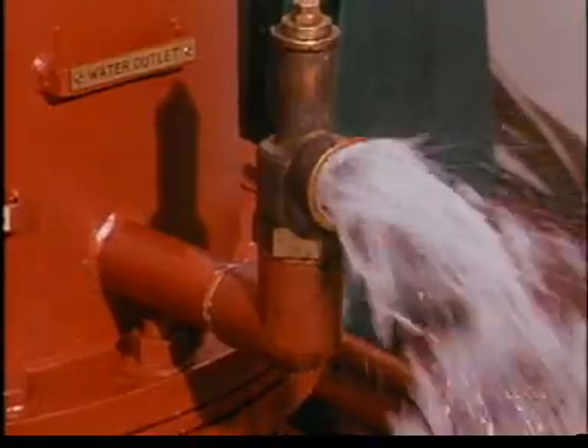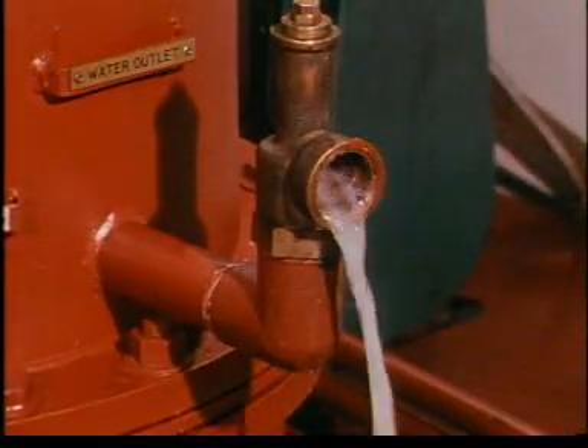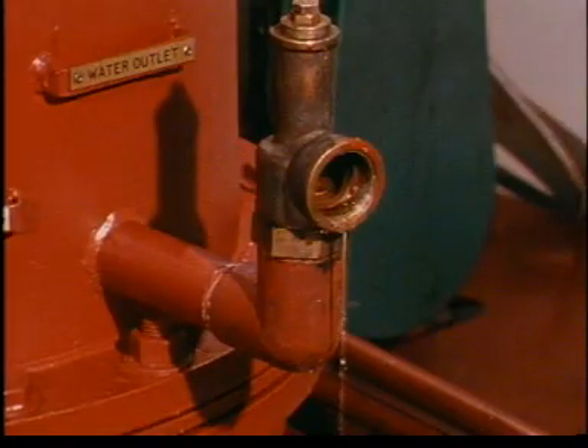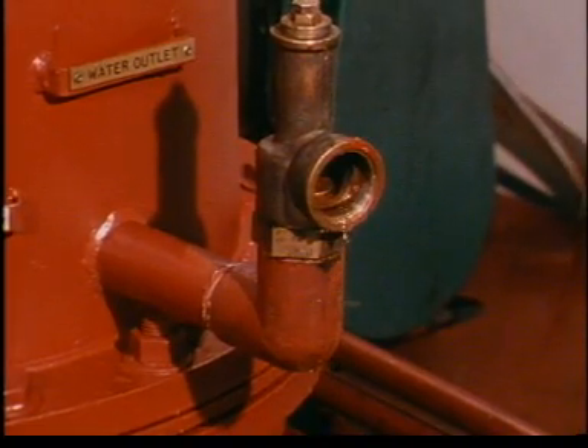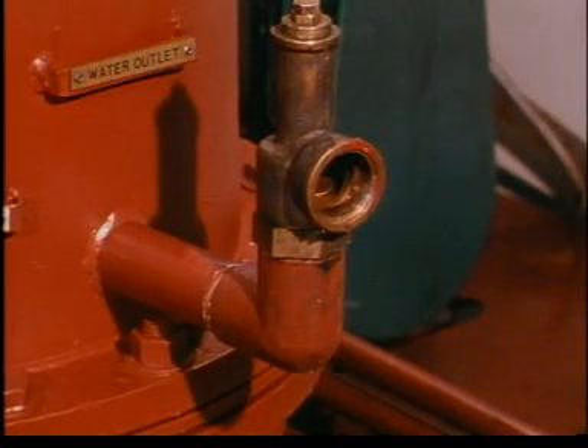There is a spring-loaded water discharge valve, which closes automatically when the pressure inside the coalescer is relieved by opening the oil outlet valve. As with the separator, oil and water are never discharged simultaneously.